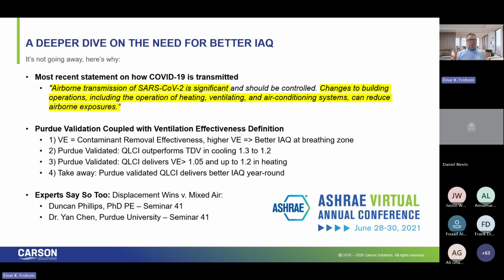And where do these numbers come from? I want to be clear that there's math and distinct calculations behind those. Those aren't just wet thumbs in the wind, but it's pretty basic math. To boil it down, it's a ratio of the contaminant level being exhausted out of the room divided by the contaminant level where the students are. So if you look at an overhead mixed air system in cooling, that might be a 1, which is defined, as in my example, as 1,000 parts per million of CO2 being exhausted, and where the students are is 1,000 parts per million of CO2.